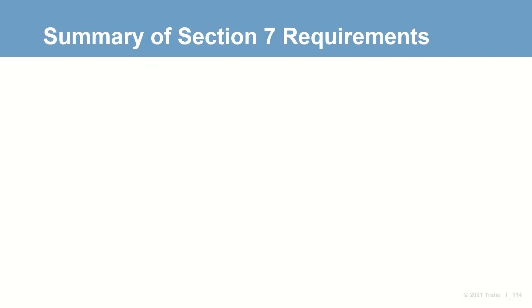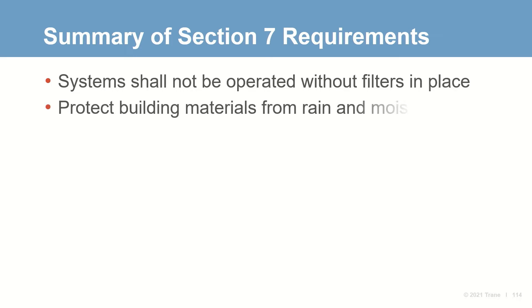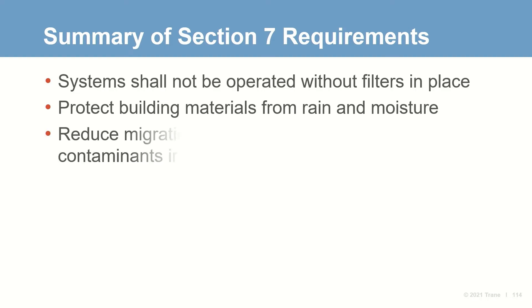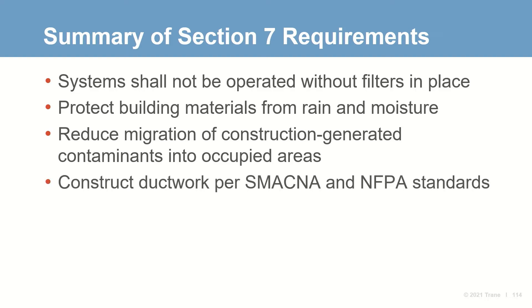During construction activity, Section 7 states that the ventilation system shall not be operated without its filter in place. It also requires you to protect building materials from rain and moisture, reduce migration of construction-generated contaminants into occupied areas, and construct ductwork per SMACNA and NFPA standards.